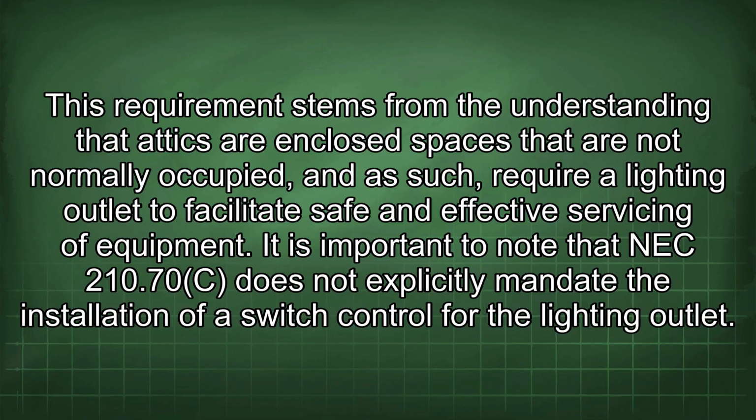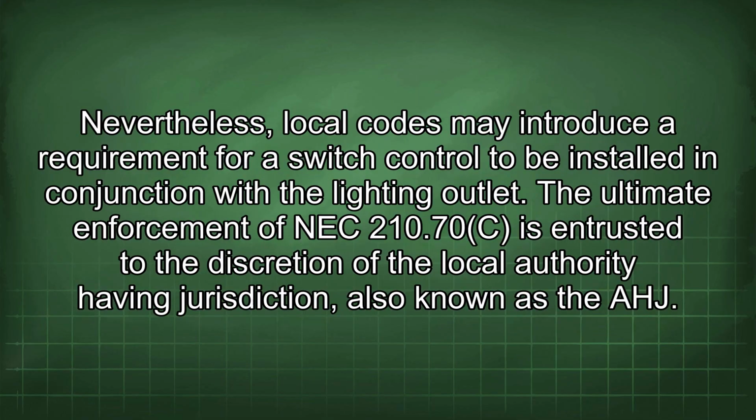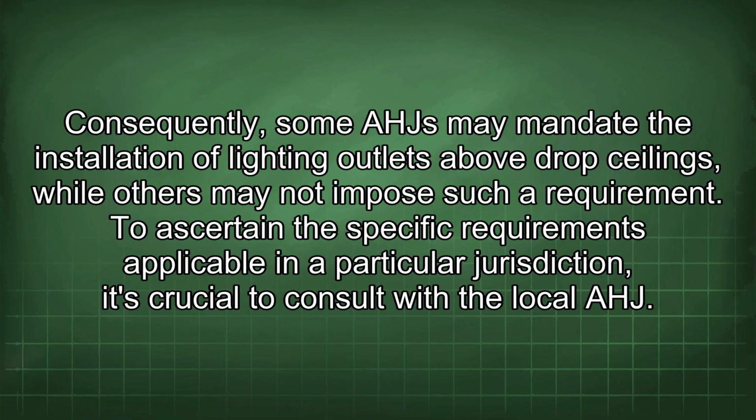It is important to note that NEC 210.70 does not explicitly mandate the installation of switch control for the lighting outlet. Nevertheless, local codes may introduce a requirement for a switch control to be installed in conjunction with the lighting outlet. The ultimate enforcement of NEC 210.70 is entrusted to the discretion of the local authority having jurisdiction, also known as the AHJ. Consequently, some AHJs may mandate the installation of lighting outlets above drop ceilings, while others may not impose such a requirement.